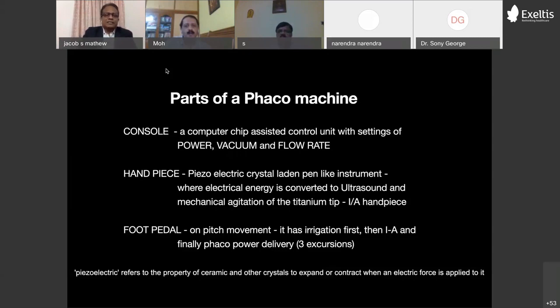The handpiece has the piezoelectric crystals, numbering from 4 to 6. Some of the machines have up to 6 crystals in it, and you can see them down below. The property of a ceramic crystal to expand or contract provides the ultrasound energy, which finally agitates the titanium tip of the phaco handpiece. You also have the irrigation aspiration handpiece, which you use after the removal of the nucleus.